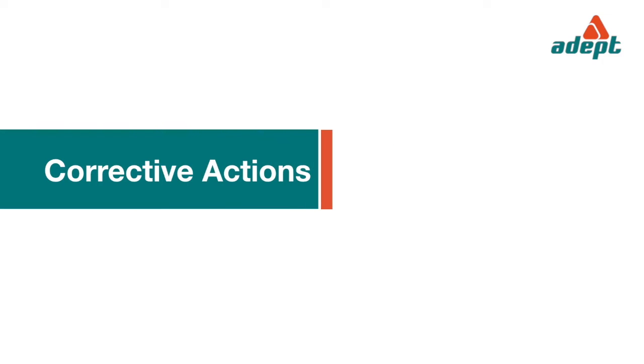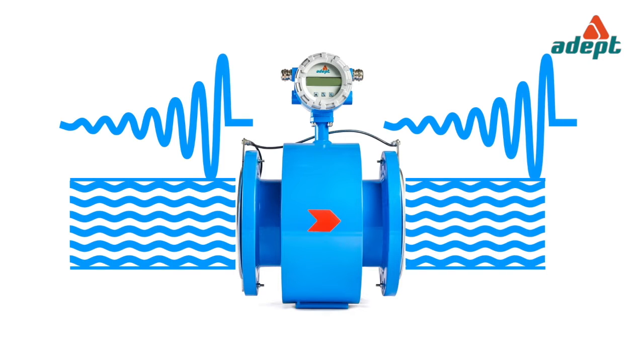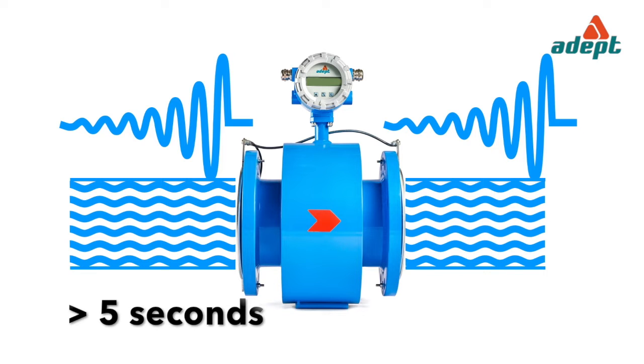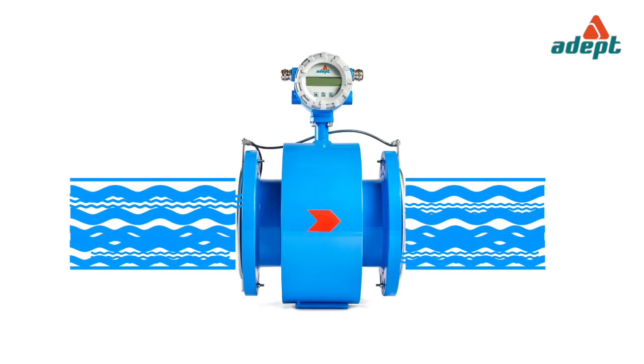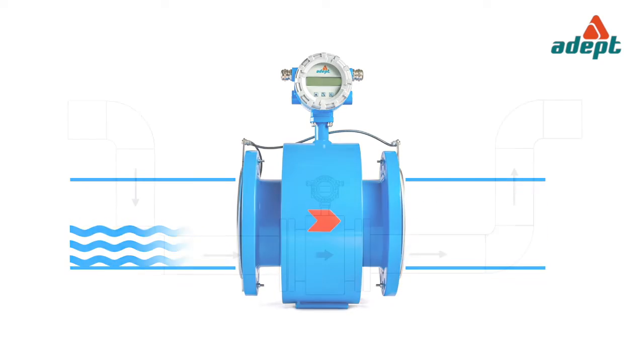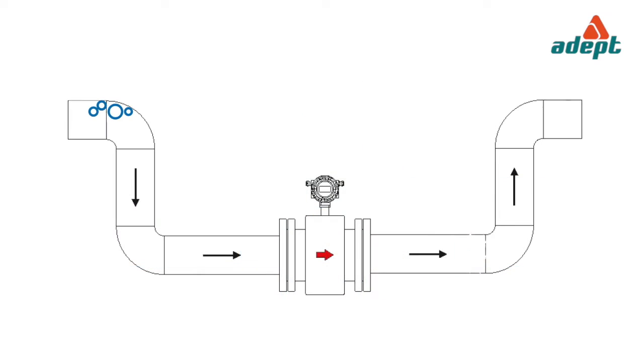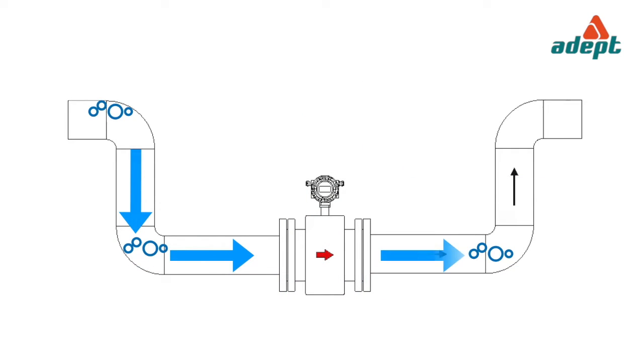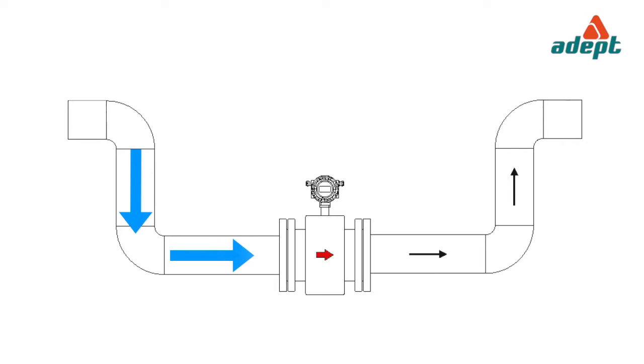Corrective actions: increase the damping factor in steps of 5 seconds and check. Allow flow to stabilize and check. Switch off feeder pipes one by one to determine the source of turbulence. Vent out excess bubbles and check. Install and orient the flow tube correctly.